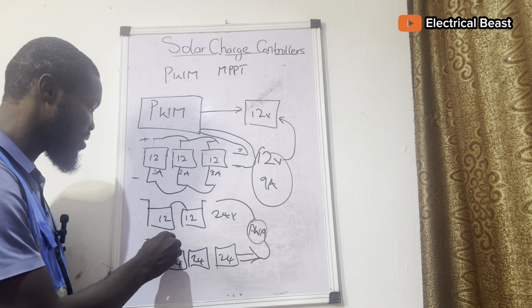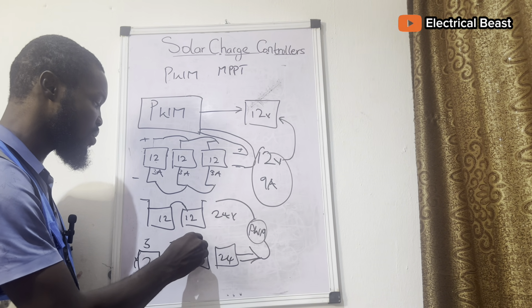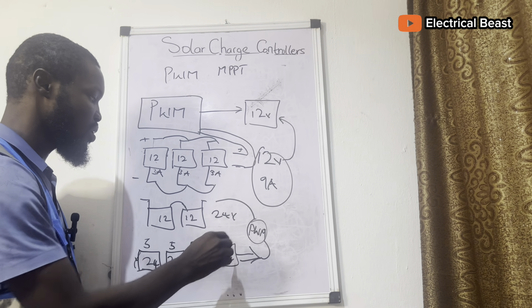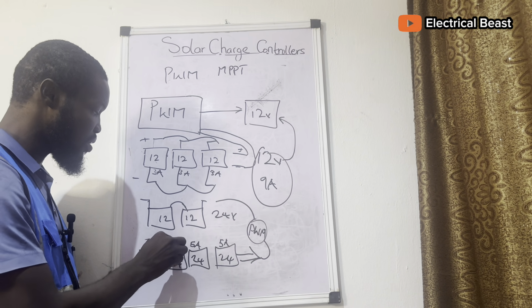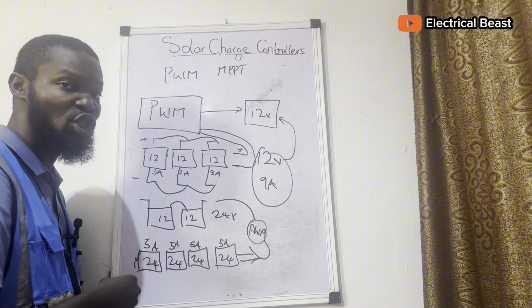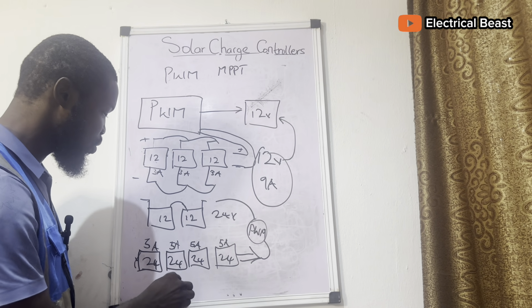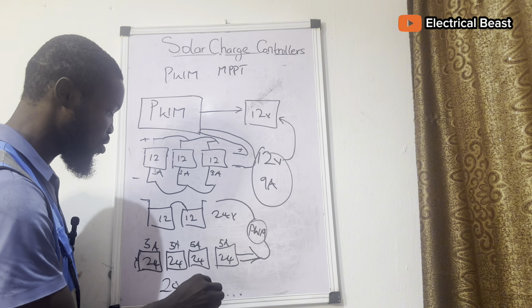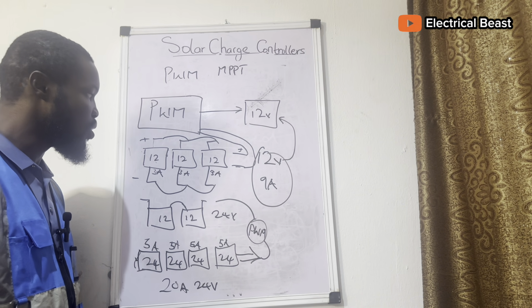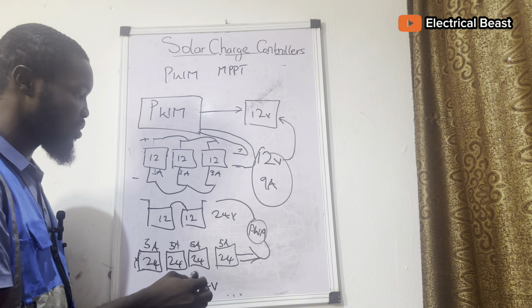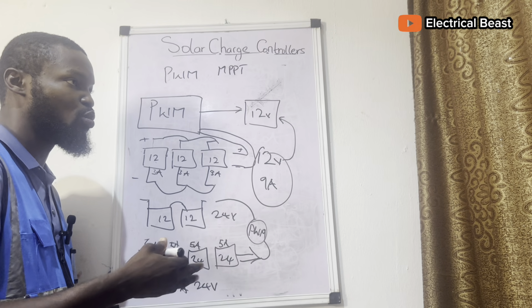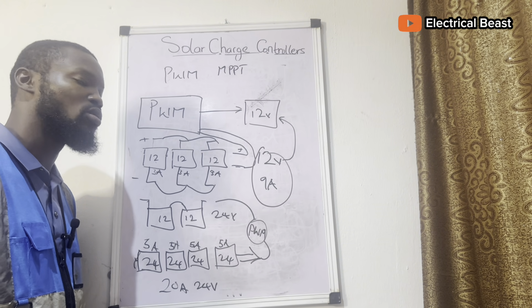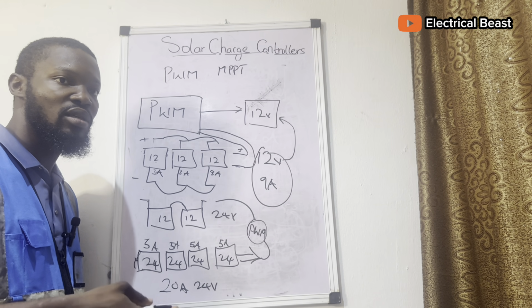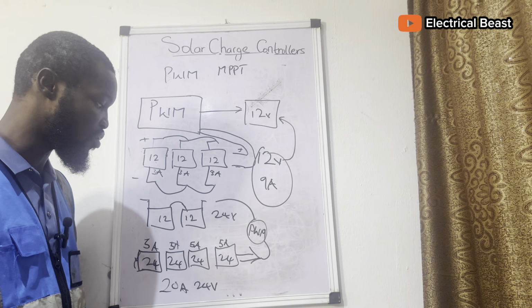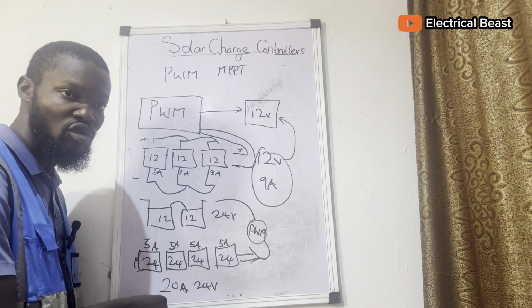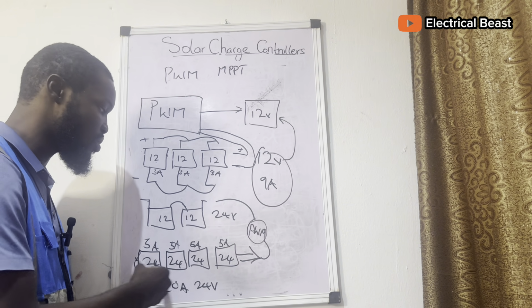If this one is, let's say, 5 amps, 5 amps, 5 amps, and 5 amps, you add up all the current together, which is 5 plus 5 plus 5 plus 5, that's 20 amps. So we have 20 amps, 24 volts. Then you can no longer use a PWM controller that is below 15 amps. You should be thinking about using 40 amps or 30 amps and above, because we have 20 amps as the maximum current that can be produced from the solar panels.